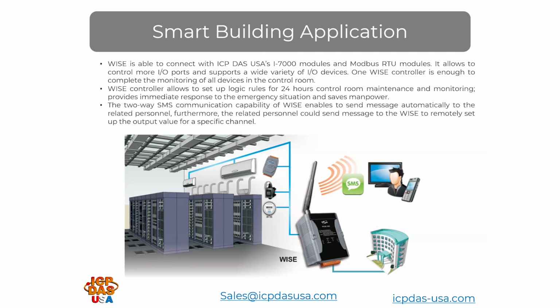Engineers can set up logic rules on the WISE controller for routine maintenance tasks, such as automatically turning on the air conditioning equipment and sending real-time alarms if the room temperature rises too high, scheduling rotation of air conditioning devices to prevent damage from prolonged operation, activating backup air conditioning if a device is detected as damaged while alerting relevant personnel.